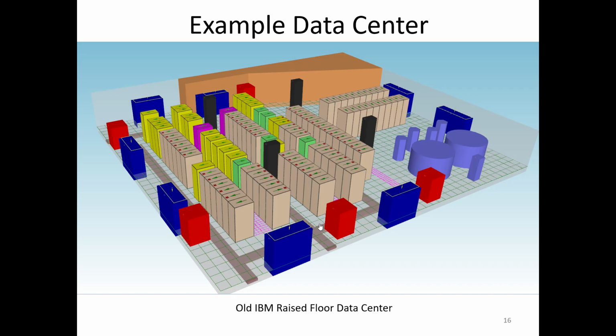There are holes in the floor. This is a raised floor design. It is a perimeter cooled design. It does not have any containment. So the air is being circulated in the room. It's being mixed. This is very characteristic of early designs that we saw.